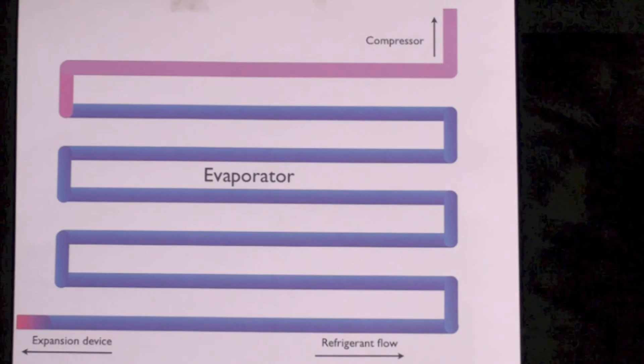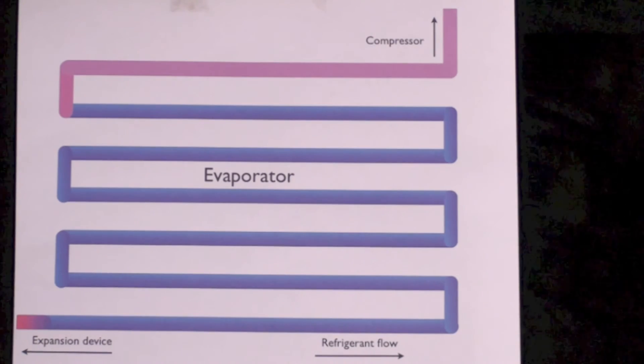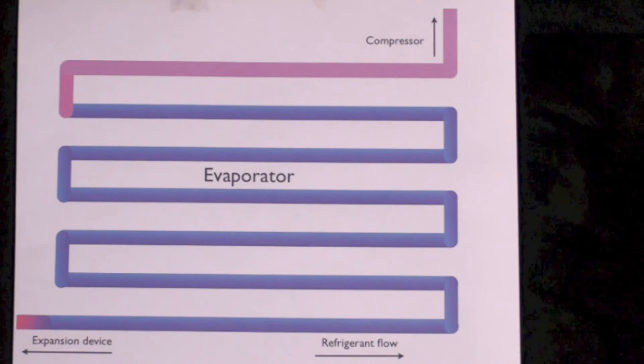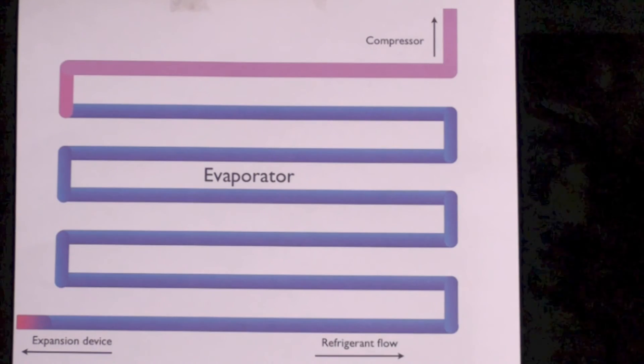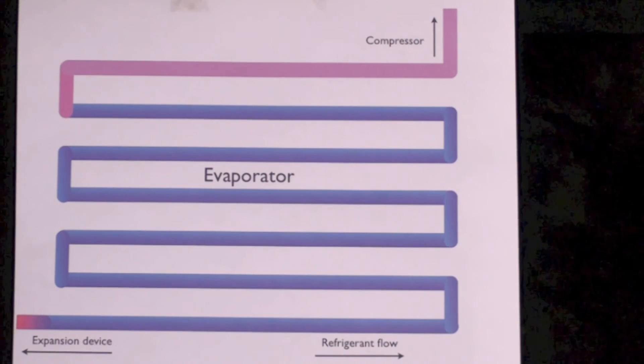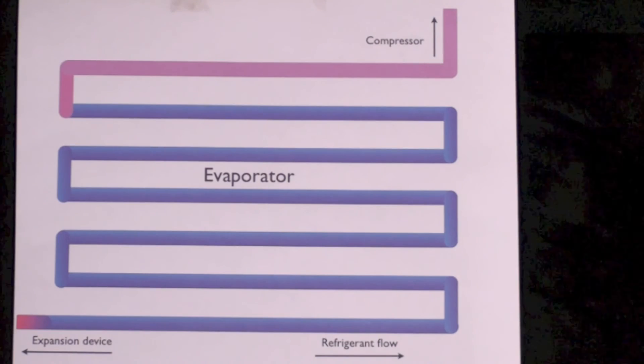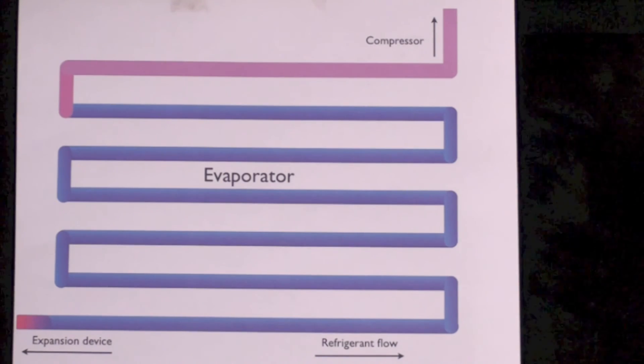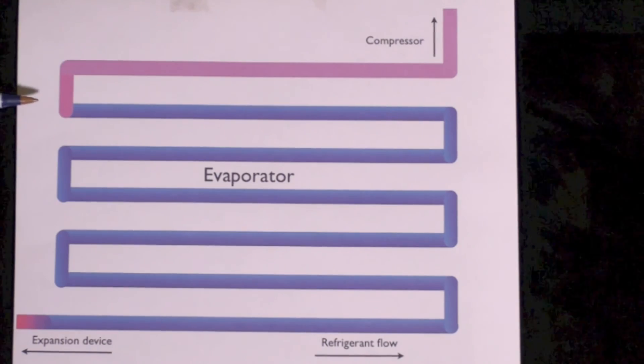So when we go to the compressor, we do not throw liquid into the compressor. We do not throw liquid into the compressor. We'll talk about liquid in compressors in another video, but liquid in compressor—bad. Makes for broken parts and all sorts of crazy things. So we try to get it so that the system does not have any liquid left in the last pass or two of the evaporator and the suction line.